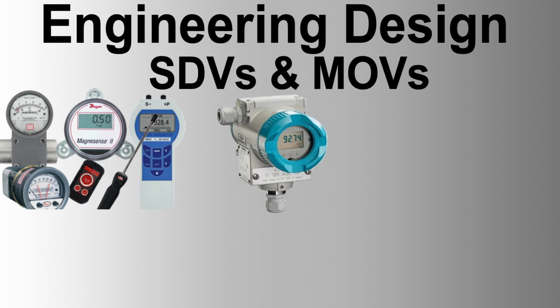Pilot-operated valves are unacceptable. Solenoid valves shall be tubed up so that on power failure, the valve moves to the failure position specified in the datasheets. Tubing and fittings. Tubing shall be of SS316L material. Tube fittings shall be of double compression ferrule type in SS316L material.